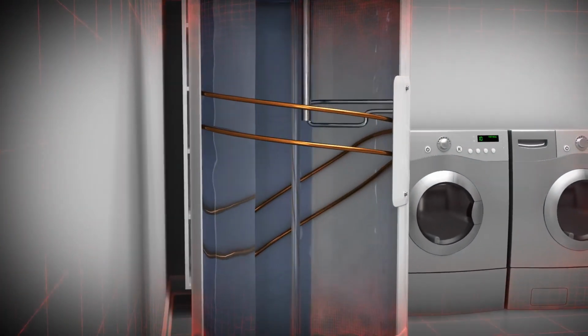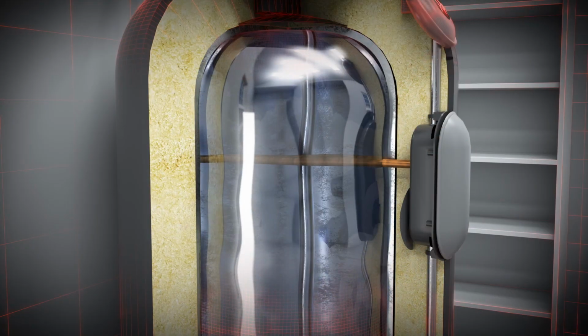If it's too small, the heat pump would short cycle, which is bad for efficiency and bad for wear and tear. Once the tank is satisfied, the heat pump shuts off. Then the heat or cool in the tank gets distributed around the house. When it's mild, this load lasts longer than at extreme temperatures. But once depleted, the heat pump will always run again for 15 to 30 minutes.